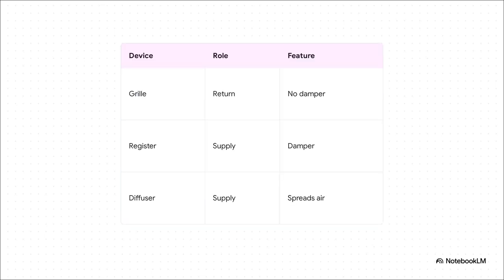Down at the actual room level, the hardware totally dictates the airflow, and the mechanical differences here are super important. A grill is a fixed opening primarily used for return air, and it's purposely left without a damper to ensure that airflow back to the system is never restricted. A register, however, includes a damper, so operators can dial in the exact supply volume with adjustable blades. And a diffuser does exactly what it sounds like. It discharges and spreads supply air wide over an area to prevent drafts and noise from disrupting sensitive equipment.